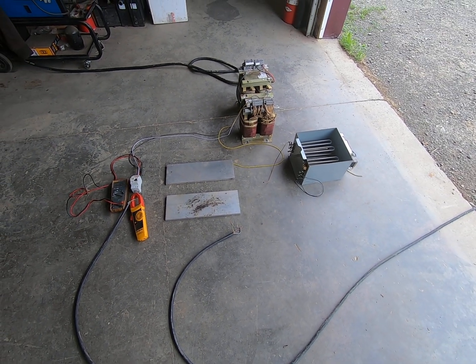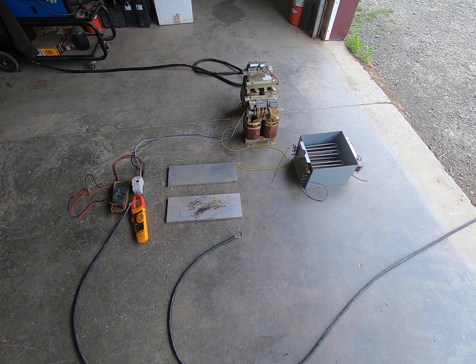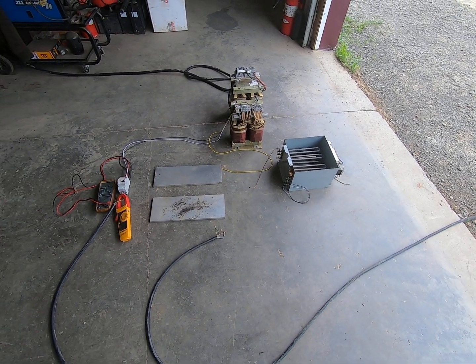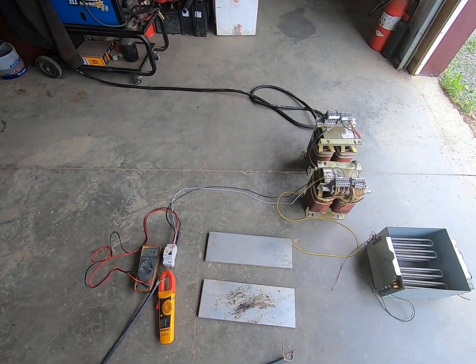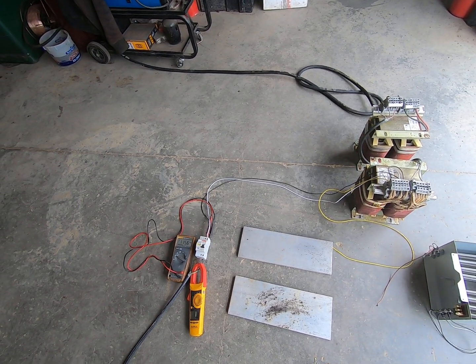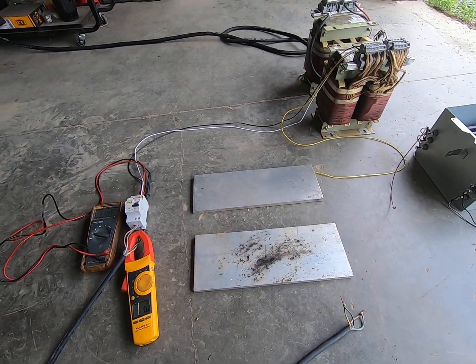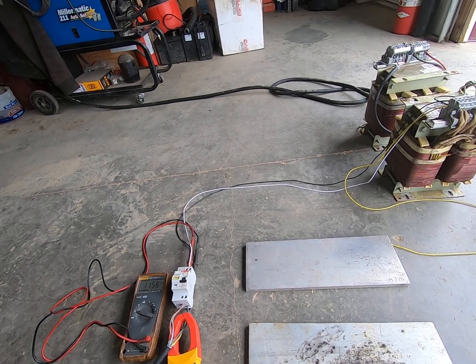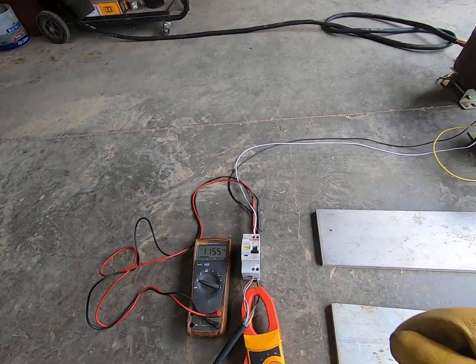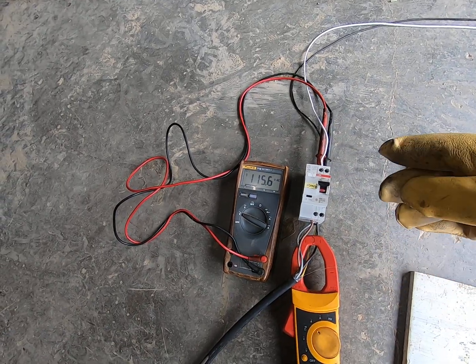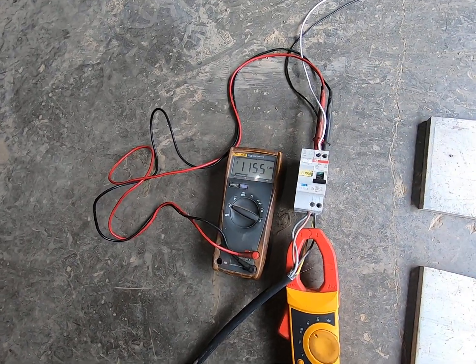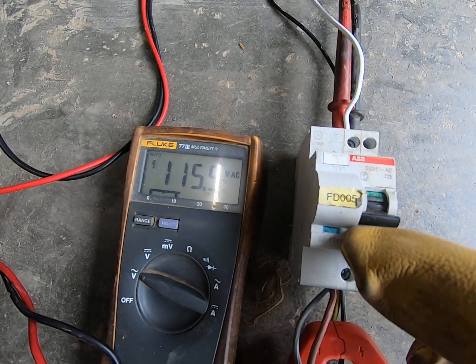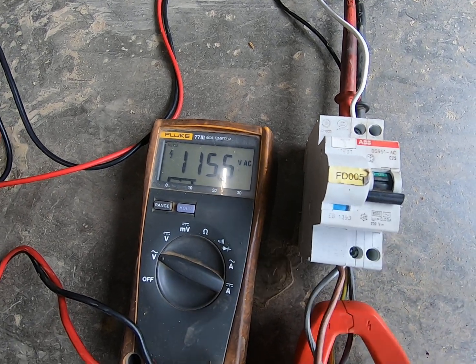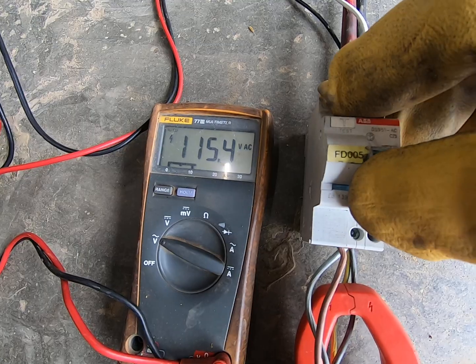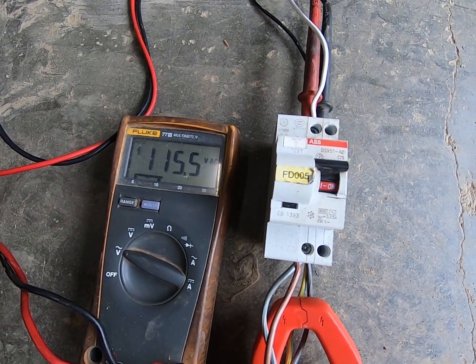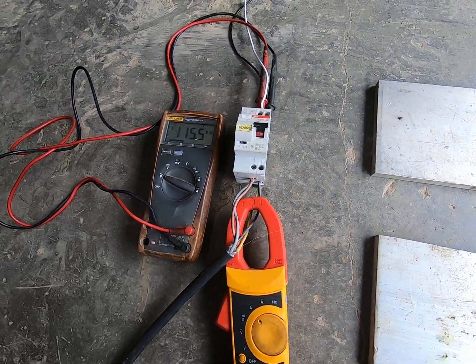The transformer I have is rated for 8400 volt amps, and the transformer in the turbine is 7000 volt amps, so it's relatively comparable. So a couple of tests I want to do here on this breaker. The very first one, probably the easiest, I'm just going to turn it on and push the test button. The breaker trips, the little window turns blue, which indicates that the little resistor inside has the ability to trip the breaker. No issue there.